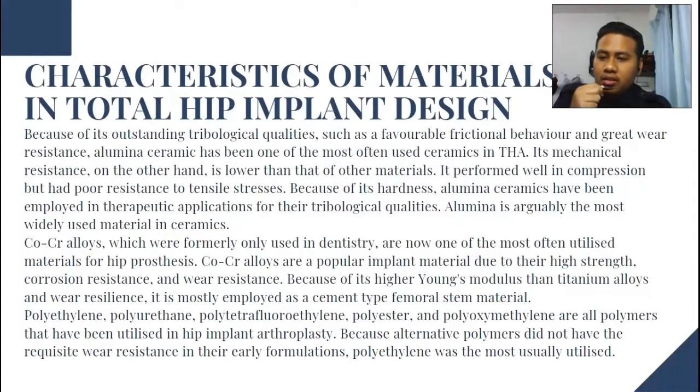Cobalt chromium alloys, which were formerly only used in dentistry, are now one of the most often utilized materials for hip prostheses. Cobalt chromium alloys are popular implant materials due to their high strength, corrosion resistance, and wear resistance. Because of its higher Young's modulus than titanium alloy and its wear resilience, it is mostly employed as a cemented-type femoral stem material.